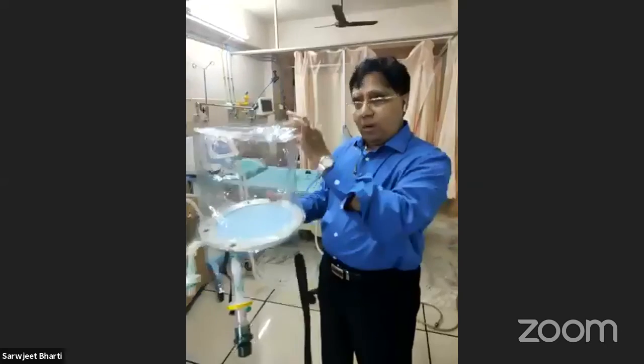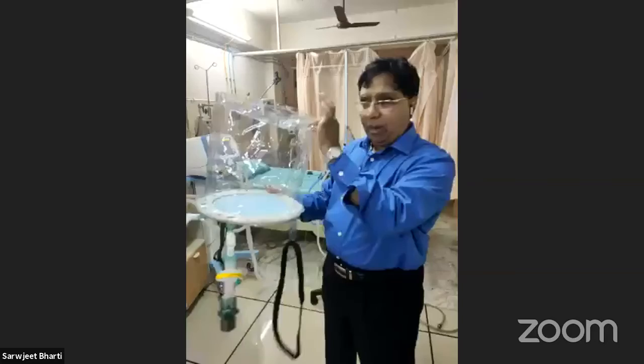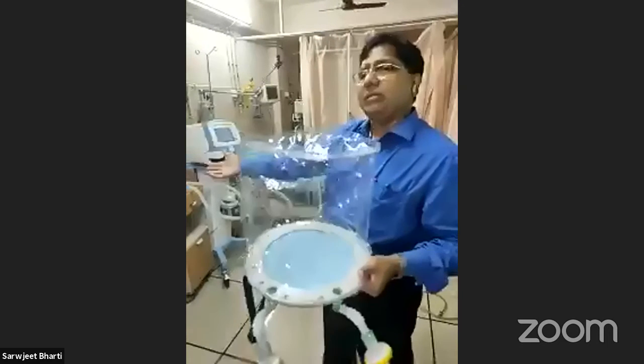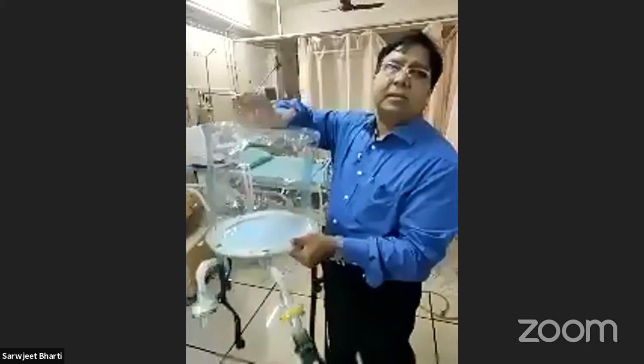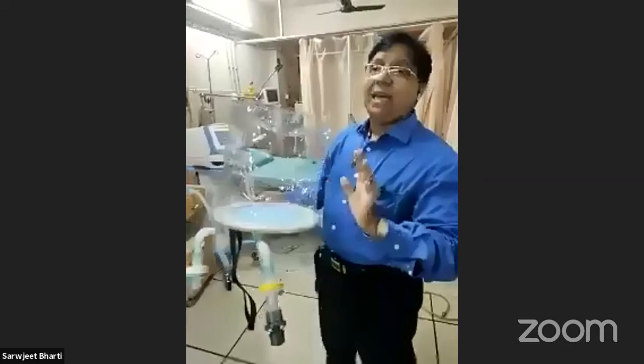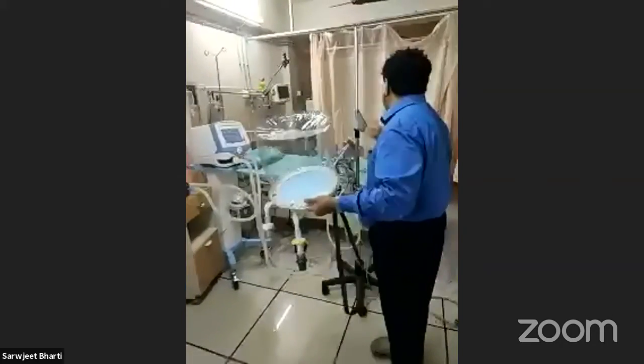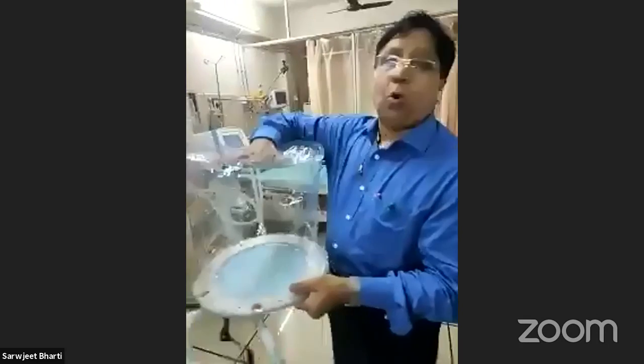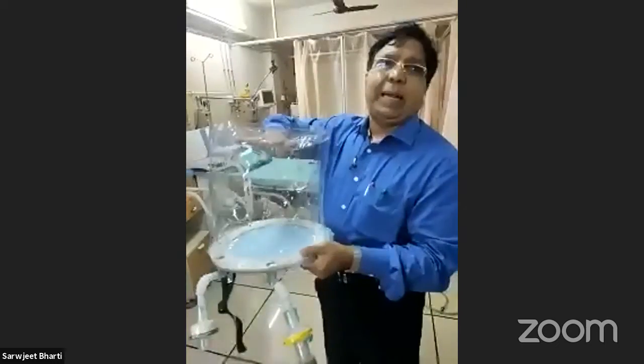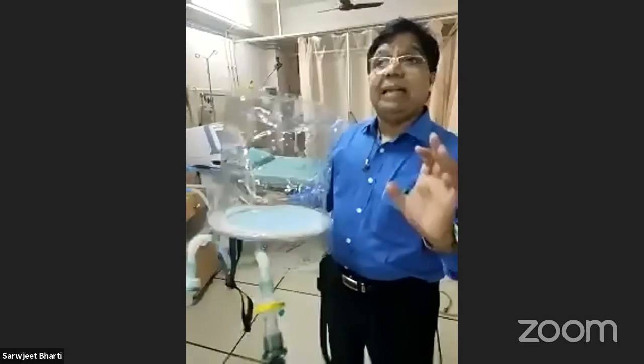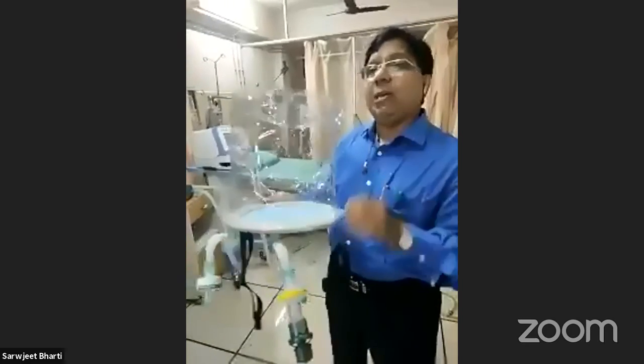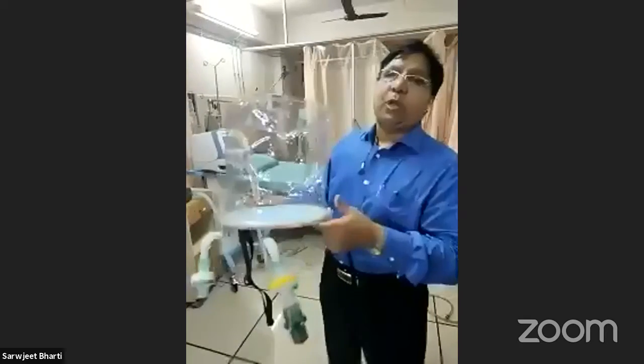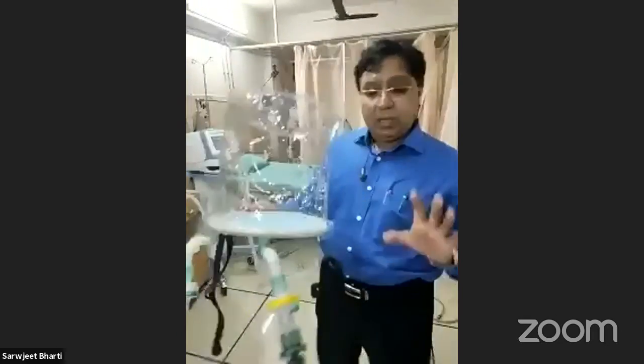The next question is, how to disinfect the device used in this method? Ideally, an oxygen bubble hood is a single-use device. It comes sterilized, either plasma sterilized, or in a scenario like today, at least it was sterilized. These are single use, and we discard them. But if we have severe shortage of availability of such devices, including the face mask or the snorkeling mask, we can reuse them by thoroughly cleaning them with sodium hypochlorite, and then use some spirit, clean it again, and re-sterilize them. But the staff who are handling these, which have been used in COVID patients, should be extremely careful. They should also be wearing PPEs, and they should take due precaution before we send them to the sterilizing department for re-sterilization. But otherwise, I would say these are all single-use medical interfaces.